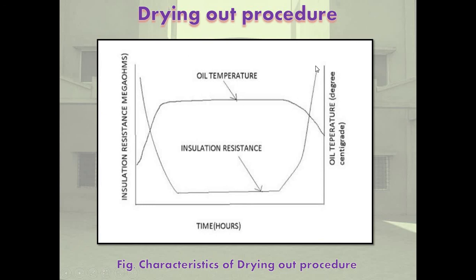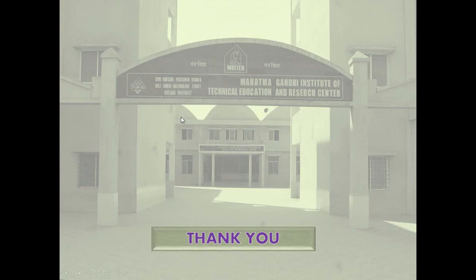This is the insulation resistance, indicating that moisture is being expelled from the equipment. So the drying out process is stopped when the desired values of hot insulation resistance and polarization index are achieved for each winding. Okay, thank you.